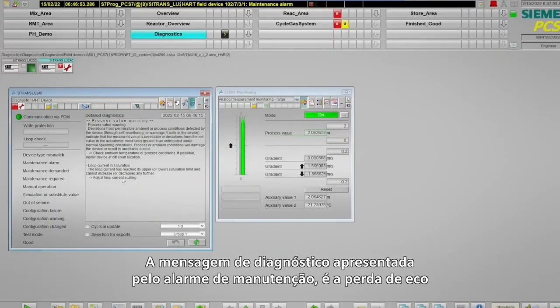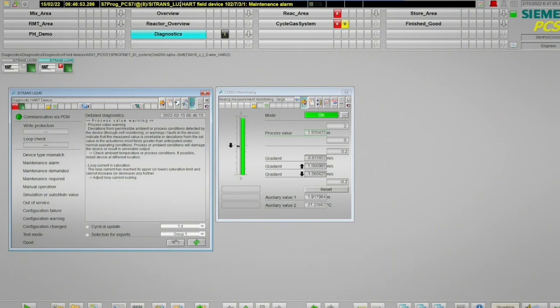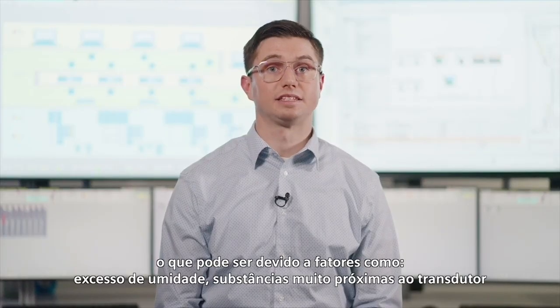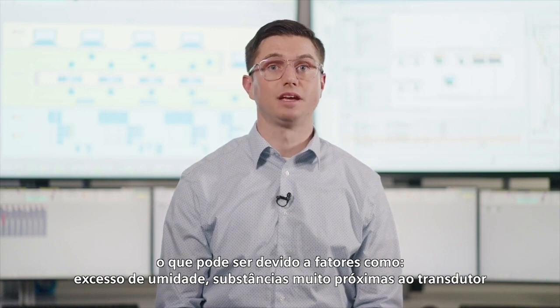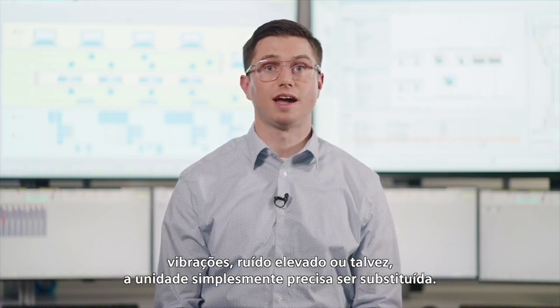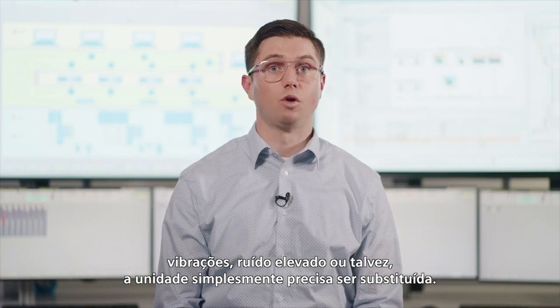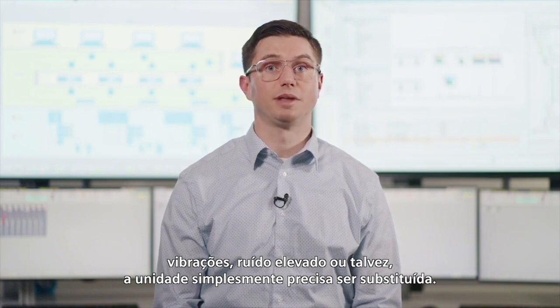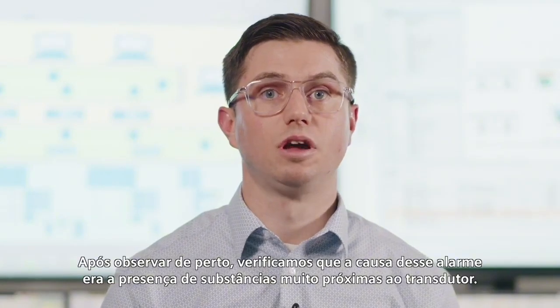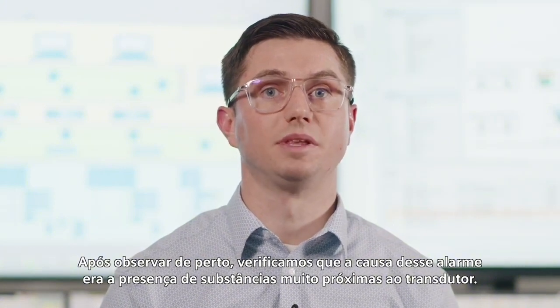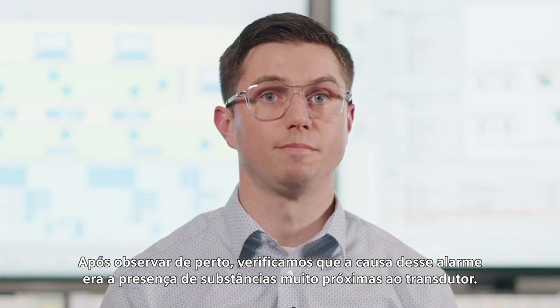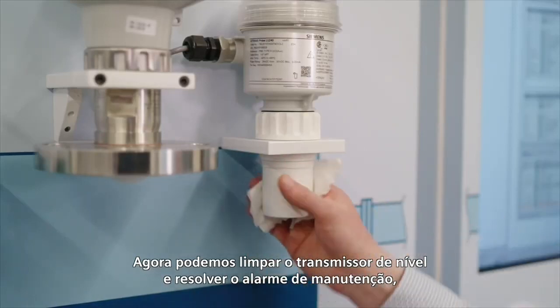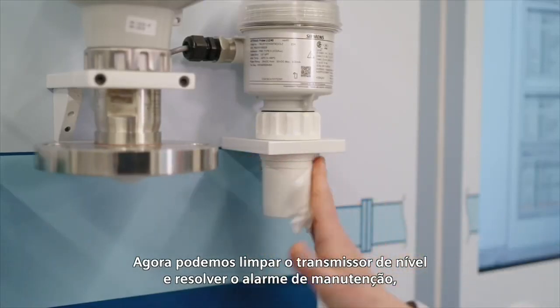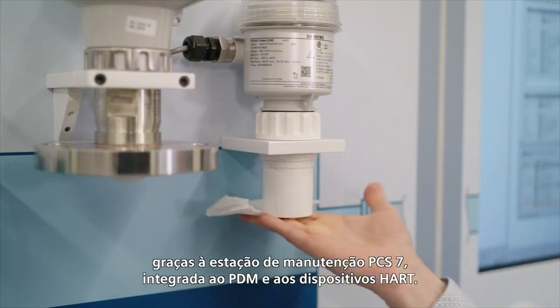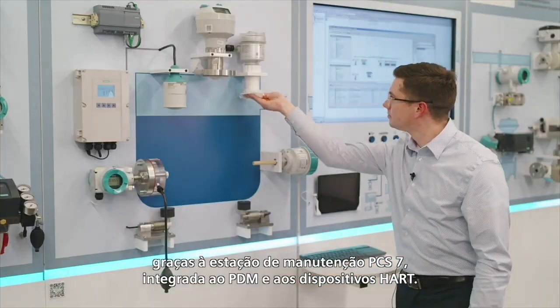The diagnostics message indicates that the maintenance alarm is from a loss of echo, which could be due to factors like excessive moisture buildup, material being too close to the transducer, vibrations, nozzle height, or maybe that this unit simply needs to be replaced. After taking a closer look, we can see that the cause of this alarm was from material being too close to the transducer. Now we can effectively clean our level transmitter and resolve our maintenance alarm thanks to the PCS7 maintenance station integrated with PDM and our HART devices.